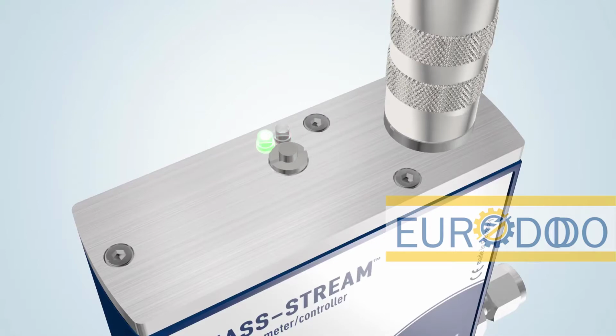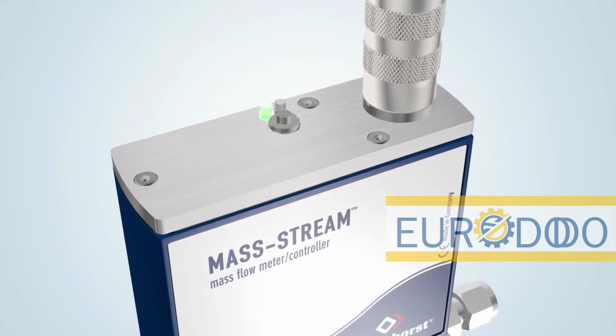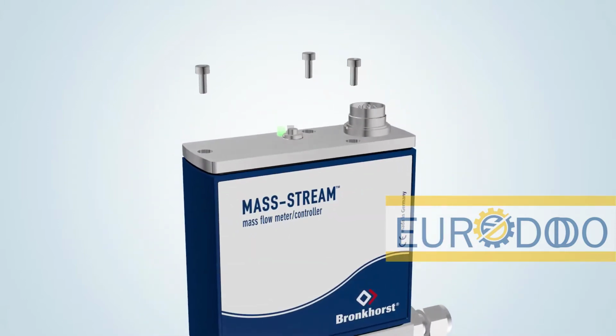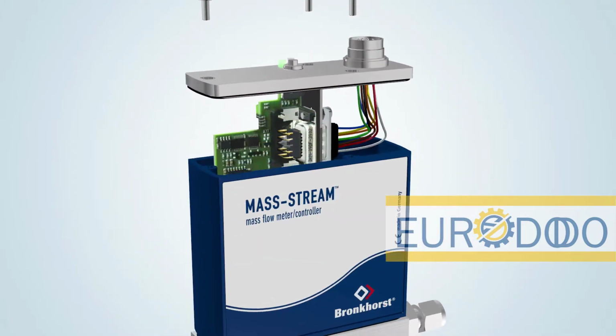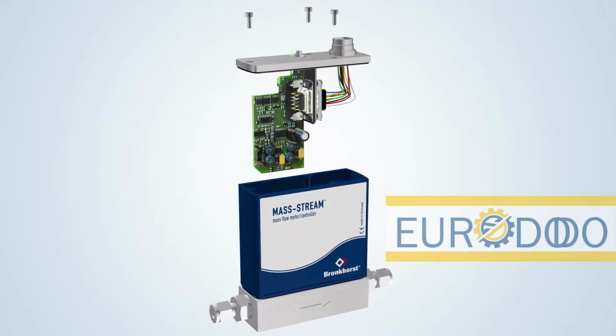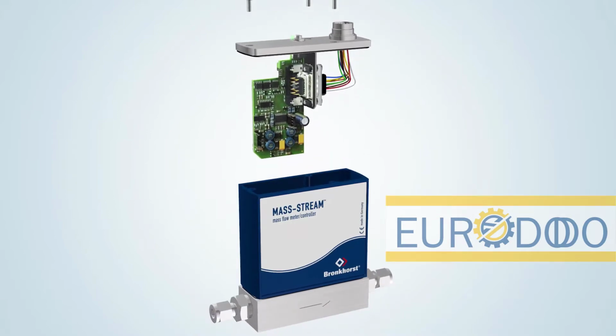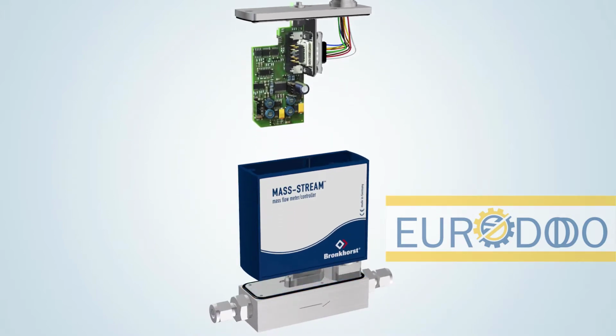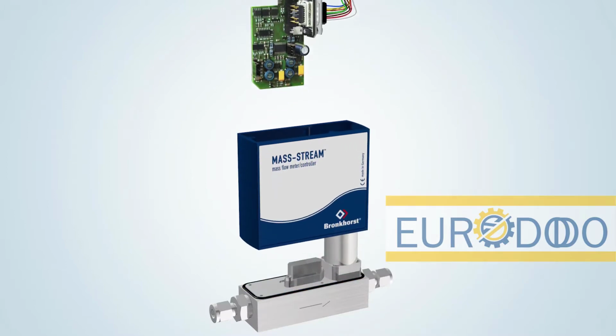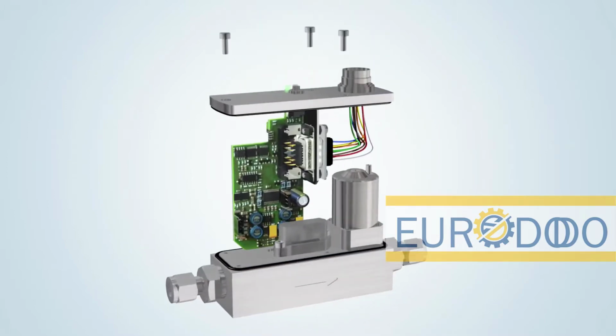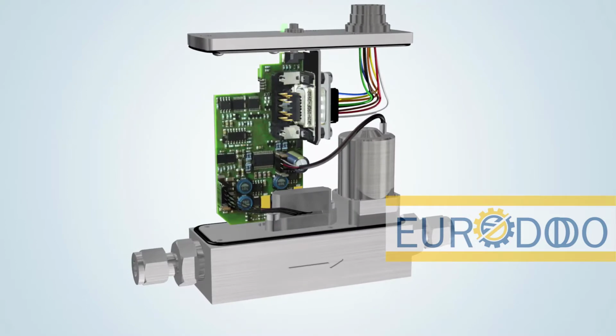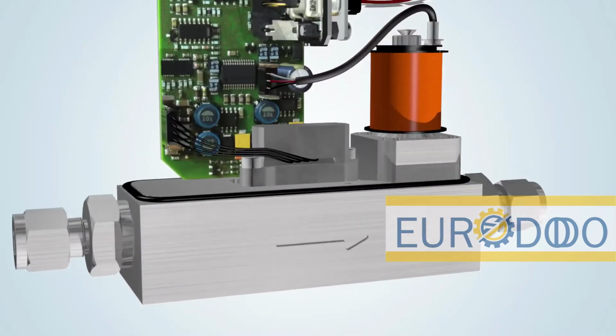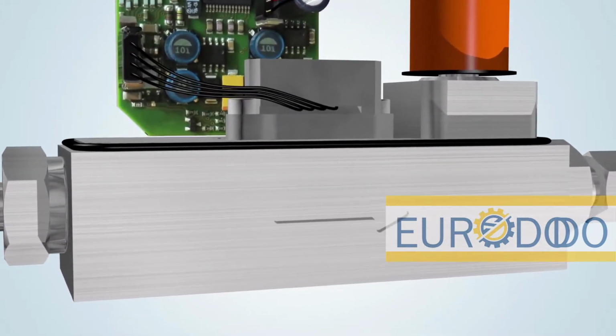After power-up, the LEDs on top of the instrument display its status. When the green LED lights up, the instrument is ready for use. Under the cover of the Mass Stream MFC is the electronics board using surface mount device technology. The measuring part of the instrument consists of a flow straightener element combined with the thermal inline mass flow sensor.